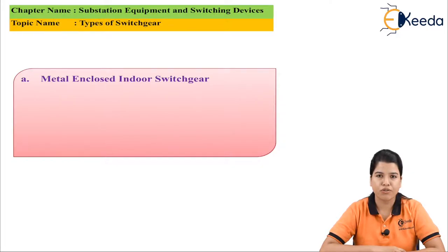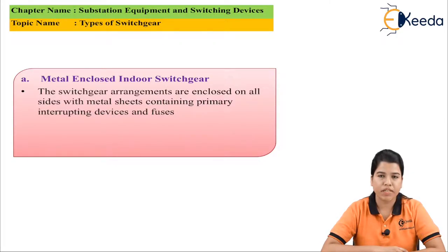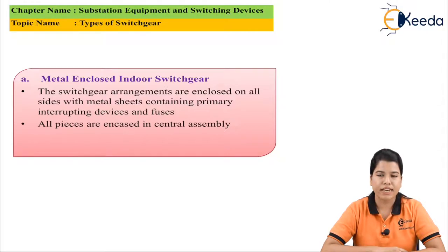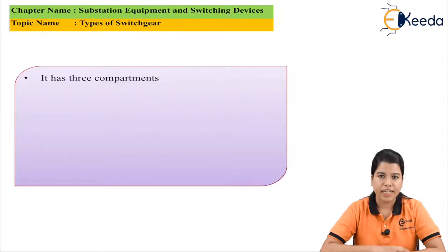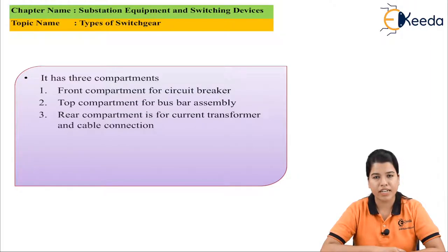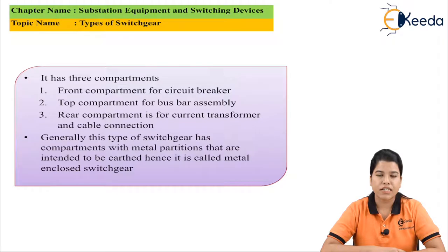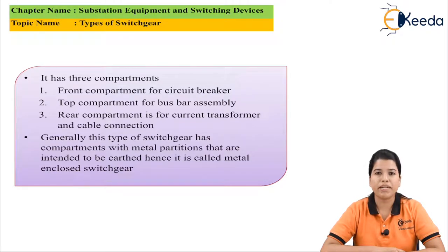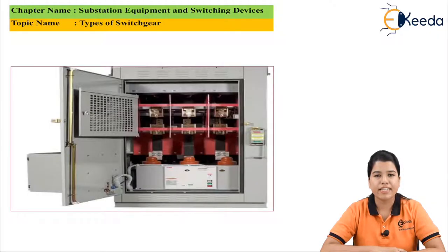Metal enclosed indoor switchgear has a metal enclosure from all sides and all pieces are enclosed in a central assembly. It basically has three compartments: the front compartment is for the circuit breaker, the top compartment is for the bus bar assembly, and the rear compartment is for the current transformer and connections. These metal compartments are grounded, hence it is called enclosed type switchgear.